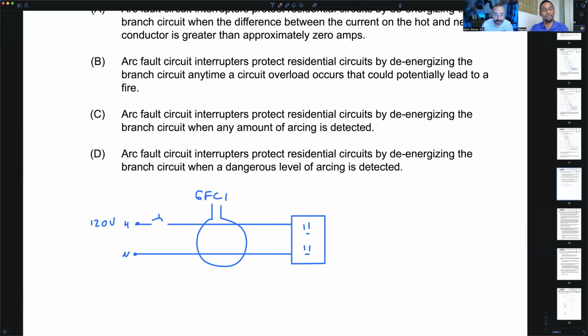In normal conditions, what's the relationship between the current on my hot conductor compared to the current on the neutral conductor for a single phase 120 volt circuit? Same current going in and out. So what current is this little current sensor going to measure if I've got the same coming in as going out? Zero. Yeah, exactly. It's going to be 0 amps.